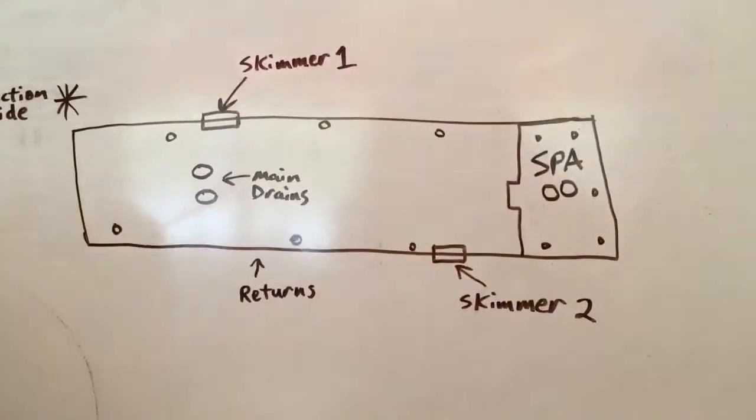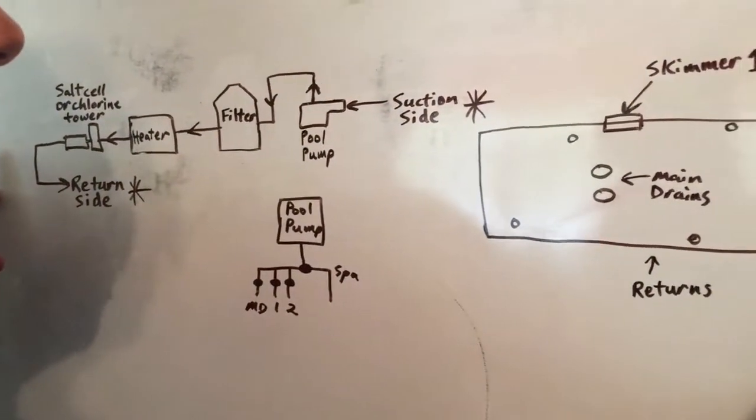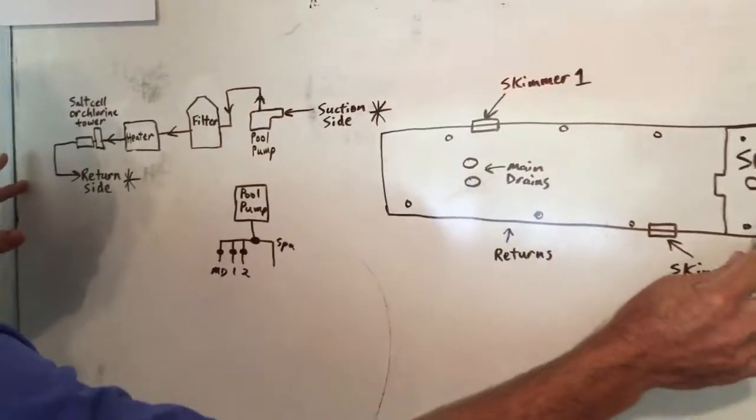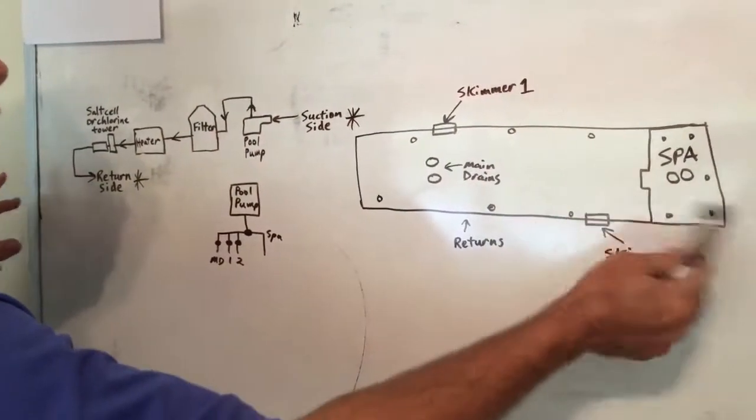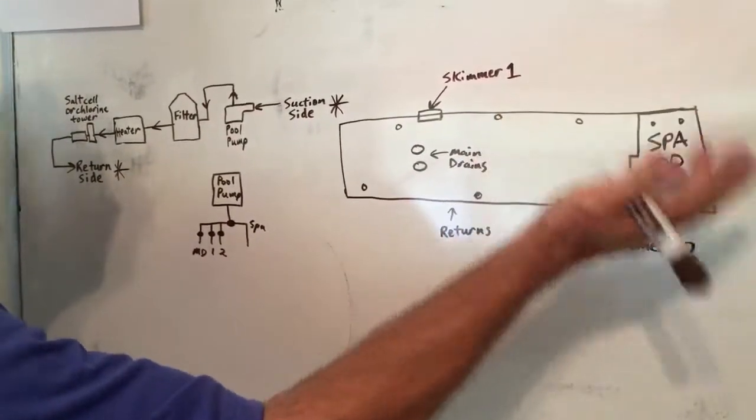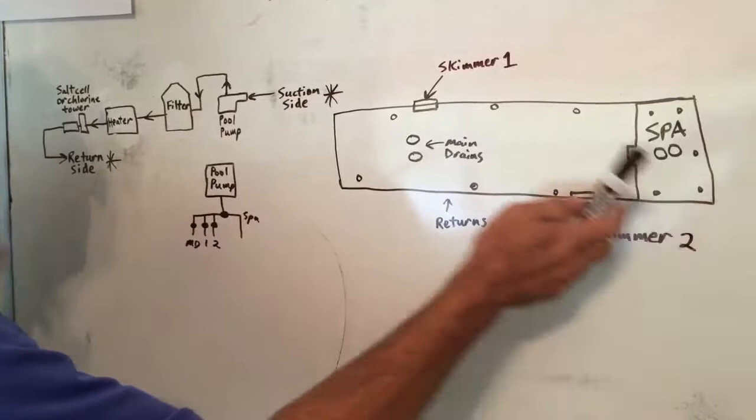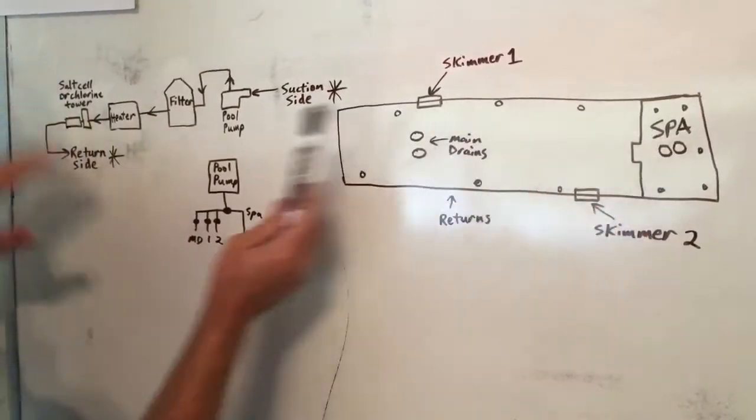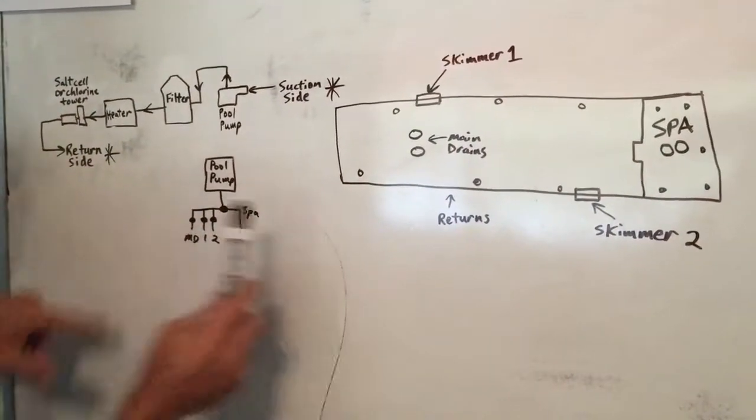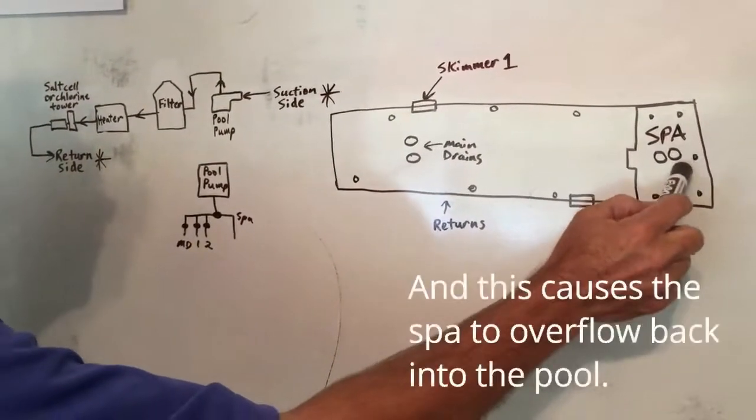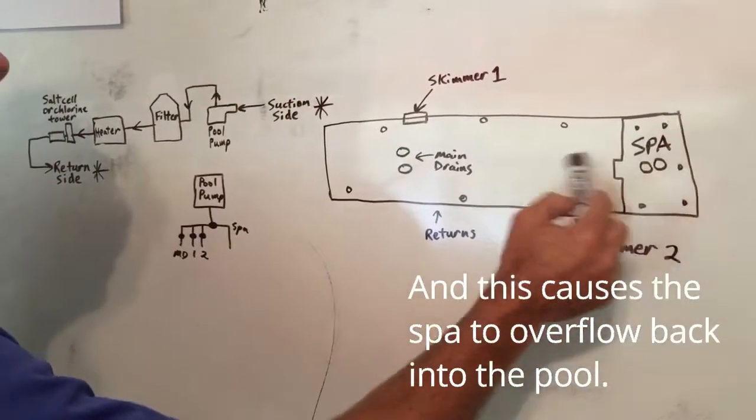One more thing to explain is sometimes there's a dedicated line on the pool side that is going to send water continually to the spa. Because we want the water to be fresh in the spa, if we never sent any water there, it would stagnate and not be good. And so when it comes back, it's going to mostly go through the pool returns. There might be one dedicated line that goes to the spa to give it fresh water.